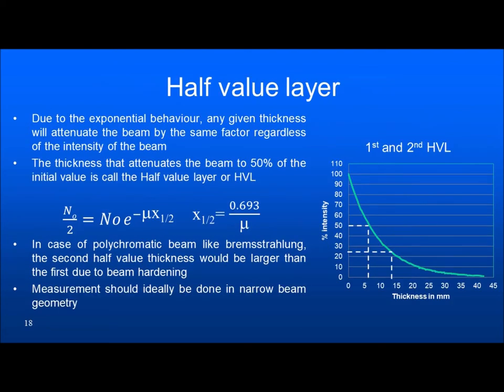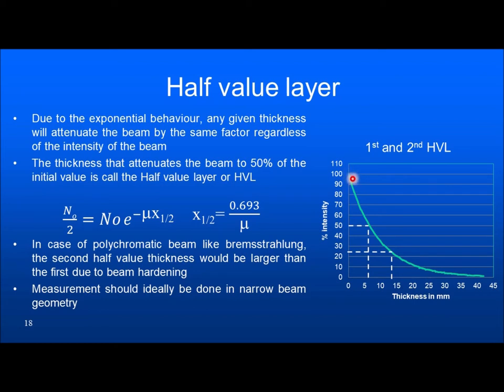The next important factor is the half value layer (HVL). Due to the exponential behavior, any given thickness will attenuate the beam by the same factor regardless of intensity. The half value layer — or half value thickness — is the thickness that attenuates the beam to 50% of its initial value. For example, here you can see that 6 mm thickness attenuates from 100 to 50 — that is the half value layer.